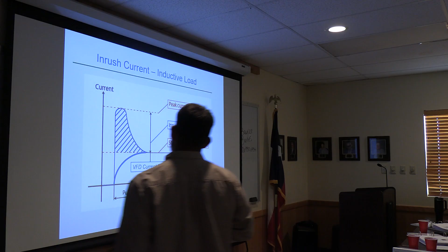by creating a ramp that goes from the zero start and getting to your steady state current once you need that steady state current. If you think of how you're pumping water, for example, you don't need the pump to spin really quick and generate all that horsepower, because you've got a pool of water that you're lifting from. If you can apply enough energy to lift that water 1 foot, then 3 foot, then 10 foot, then 100 foot, you get that chance to ramp into that load.